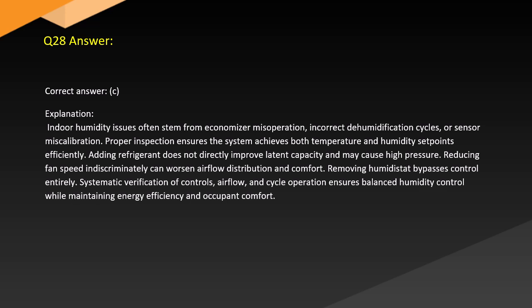Answer. Correct answer. C. Explanation. Indoor humidity issues often stem from economizer misoperation, incorrect dehumidification cycles, or sensor miscalibration. Proper inspection ensures the system achieves both temperature and humidity set points efficiently. Adding refrigerant does not directly improve latent capacity and may cause high pressure. Reducing fan speed indiscriminately can worsen airflow distribution and comfort. Removing the humidistat bypasses control entirely. Systematic verification of controls, airflow, and cycle operation ensures balanced humidity control while maintaining energy efficiency and occupant comfort.